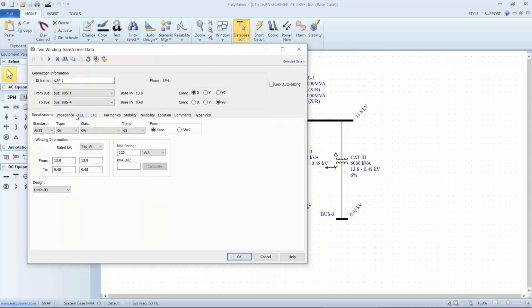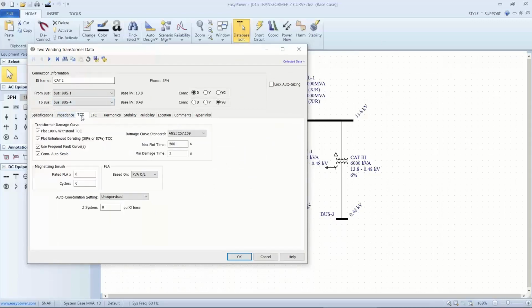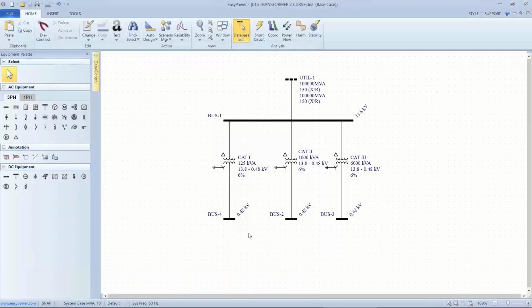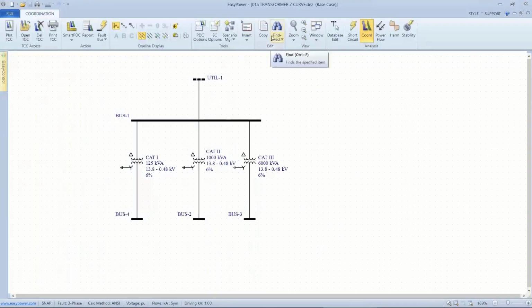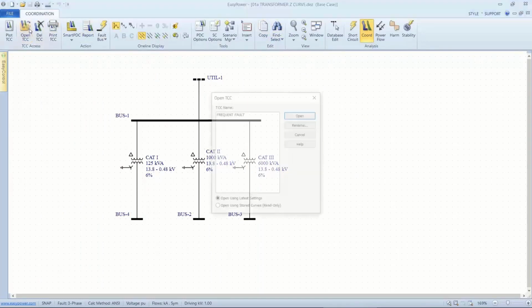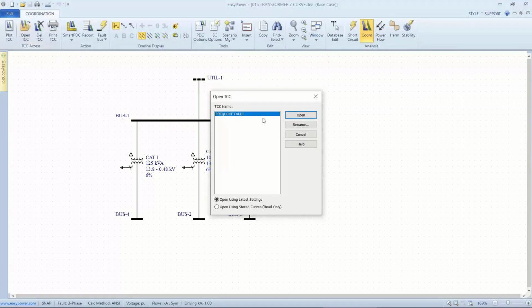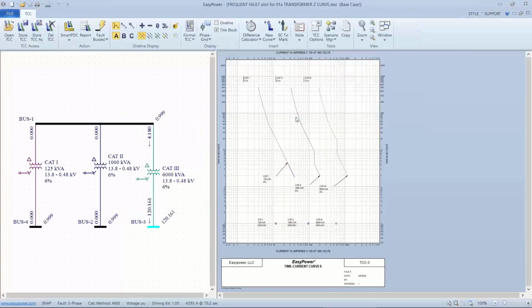Now the point I'm trying to make is that once we've got the data entered, when we go to plot the TCC curves, by default, all 4 of these check boxes are filled in. And that gives us a TCC plot that looks like this. The module that we use for coordination, we refer to as protection and coordination, and it allows us to save TCCs. So I've already created this TCC plot showing all 3 transformers.